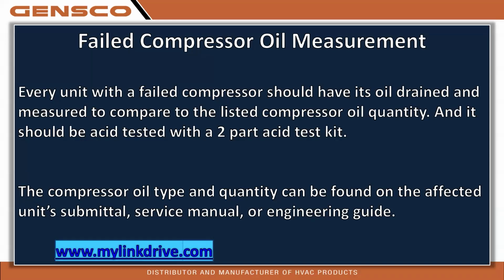If it was an electrical failure, you're going to want to acid test that. Not all electrical failures in systems that use POE or PVE oil will produce acid. It requires moisture to be present for that to occur. You may have an electrical failure in a good dry system where the compressor shorted to ground and the oil may even be dark, but it may not be acidic if there's no water available for that to form.